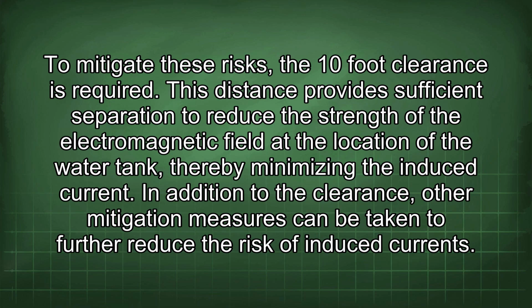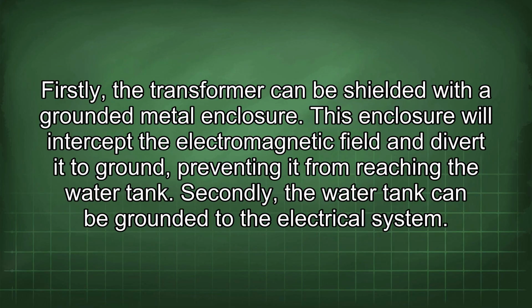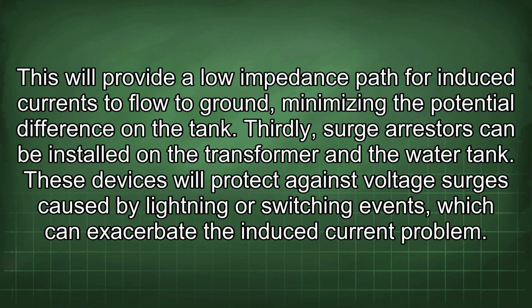In addition to the clearance, other mitigation measures can be taken to further reduce the risk of induced currents. Firstly, the transformer can be shielded with a grounded metal enclosure. This enclosure will intercept the electromagnetic field and divert it to ground, preventing it from reaching the water tank. Secondly, the water tank can be grounded to the electrical system.